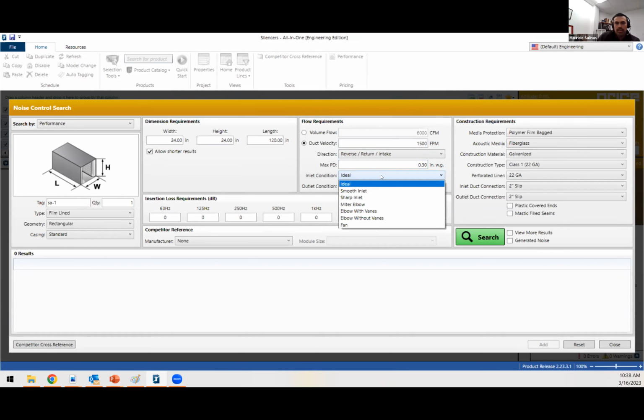So what is the location of the silencer relative to the next element in the ductwork, right? So if you think about the test standard ASTM E477, you have 5 equivalent duct diameters at the inlet from the silencer to the next duct element, and 10 equivalent duct diameters at the outlet. That is that perfect lab ideal condition. You typically don't have that. Right, so if this is really close on the vertical to the rooftop unit within 5 equivalent duct diameters, then your inlet condition for a forward flow on the supply is going to be fine.